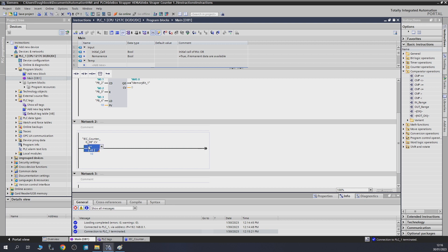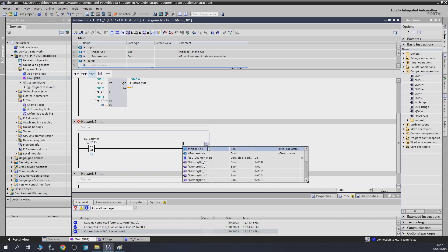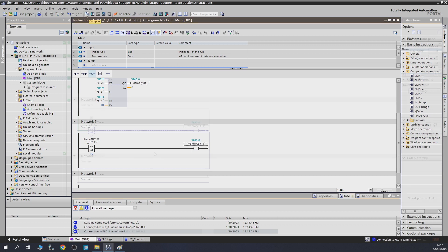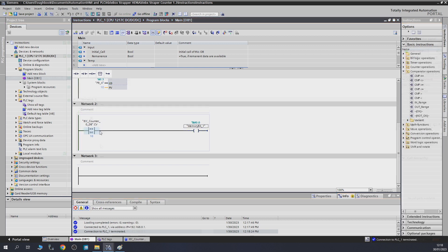By double-clicking on the top you can change between different compare types. This compare block can handle many different data types; for now we're sticking with integer values — solid values with no decimals. We give it a memory bit coil to activate. At the moment, the top value is zero and the bottom is 10, so the output is off. If we count up to 10, the output comes on and stays on as long as both values equal 10. Above or below 10, the output turns off — that is the Equal comparator.